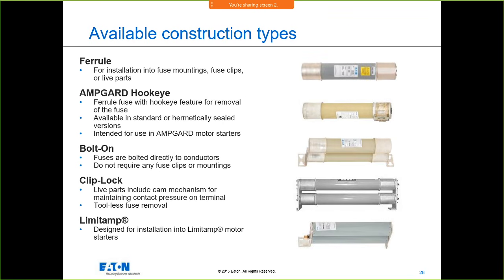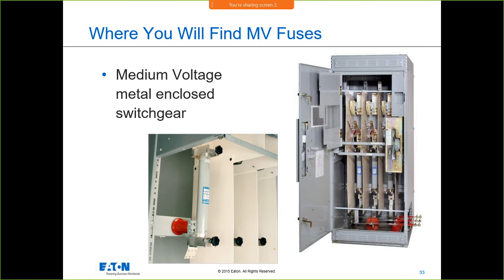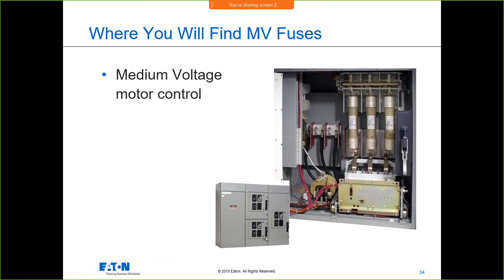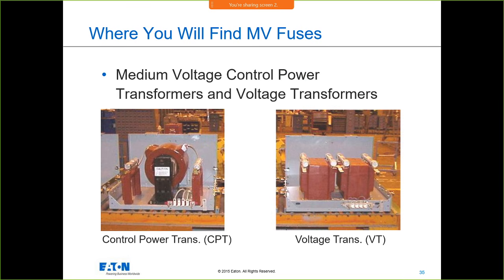I'm not going to get through catalog numbers, but when you're picking these fuses, you have to think about the mounting configurations, whether it's bolt-on, clip, and all that good stuff. Those are going to be important parameter points, because the equipment you're putting it in will determine them. For example, medium voltage metal enclosed switchgear will have a way to mount that equipment depending upon the manufacturer. They'll sometimes have their own mounting mechanisms in that equipment. So you're going to want to make sure you match the mounting mechanisms with those installed units.